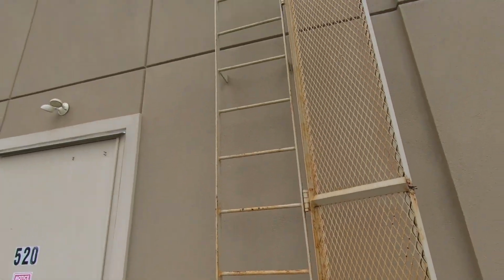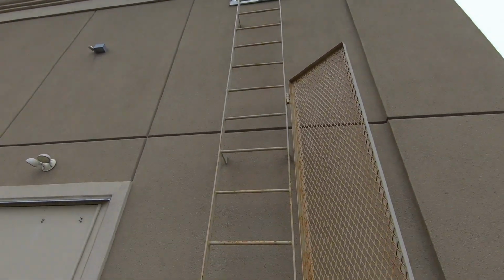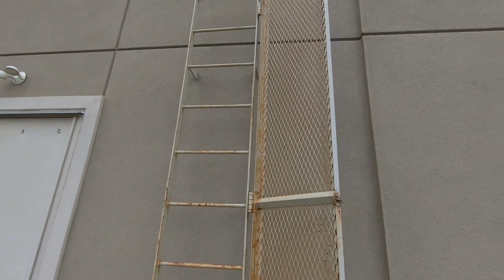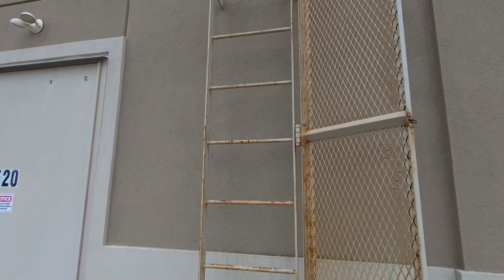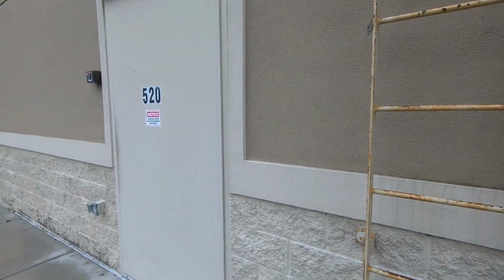All right, I'm assuming the fire department shut off breaker 1 as well. Disconnect on unit 1 was here. The breaker panel was marked 1, but it's actually power in unit 2. So I think it was just a miscommunication with the labeling. I don't know. I labeled them the same way they were labeled on the roof, but they're just flip-flopped in the panel, so no big deal. All right. I think we dodged a bullet there.